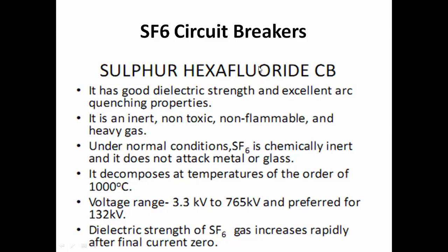It is an inert gas, it is a non-toxic gas, it is a non-flammable gas, and it is a heavy gas. So sulfur hexafluoride has these properties: it is inert in nature, non-toxic in nature, non-flammable, and it is a heavy gas. Due to all these properties, this gas can be used as an arc quenching media in a circuit breaker. Under normal conditions, sulfur hexafluoride gas is chemically inert and does not attack any metal or glass. It decomposes at a temperature of the order of 1000 degrees centigrade.